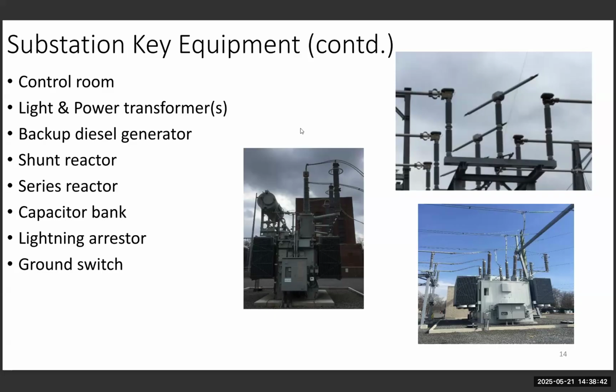So one lesson learned from Superstorm Sandy, for those of you who were there a long time ago: the station light and power does exactly what it said, light and power. It's a very small transformer that provides local usage. Basically, if the station goes down, the station light and power could be utilized to charge the batteries for the battery room, lights, computers, stuff like that. So it's very important. One of the lessons learned from Superstorm Sandy was that if you have an oil-filled system, you need to already have either a backup diesel generator on site or have the connection ready.